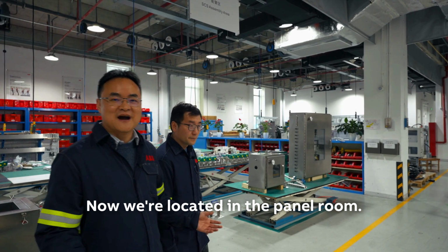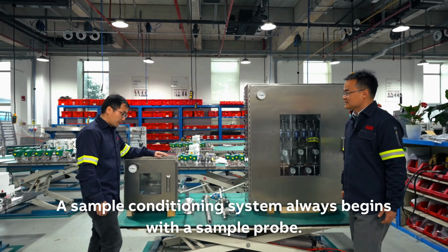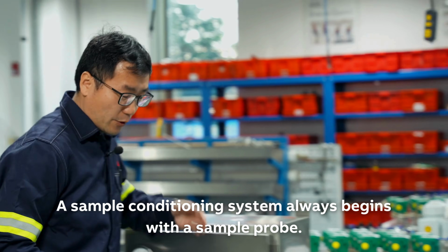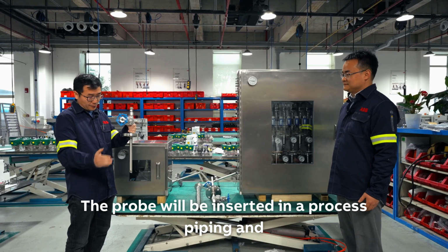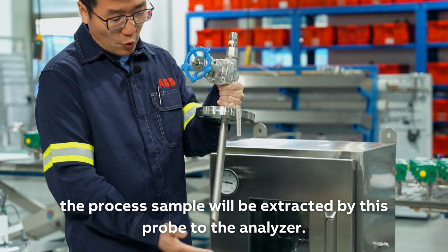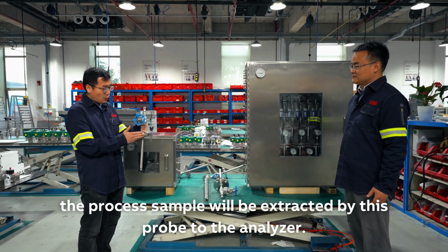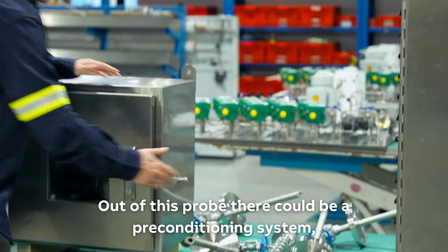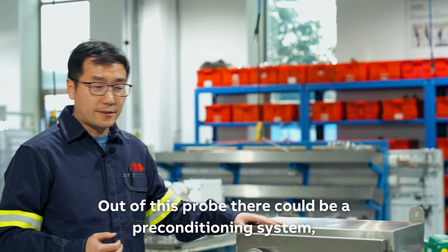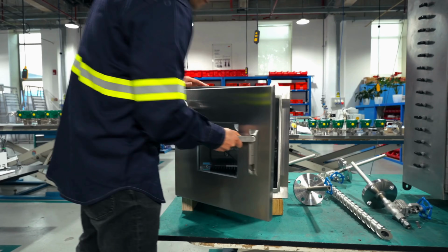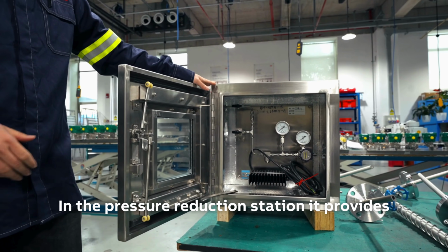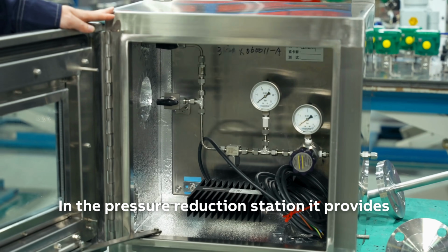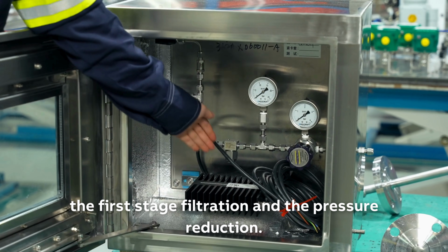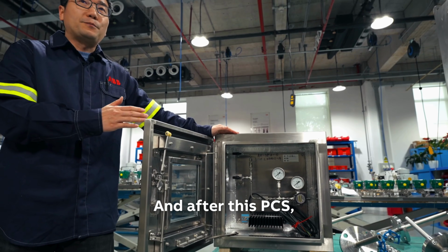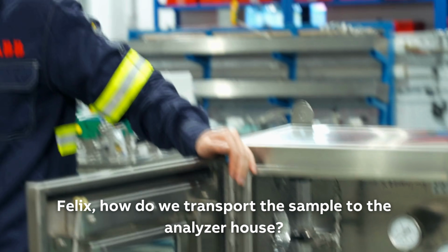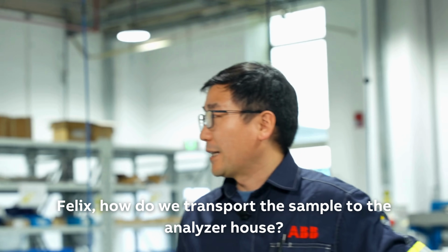Now we're located in the panel room. A sample conditioning system always begins with a sample probe. The probe will be inserted in a process piping, and the process sample will be extracted by this probe to the analyzer. After this probe, there could be a preconditioning system, a pressure reduction station. The pressure reduction station provides the first stage filtration and the pressure reduction. And after this PCS, Felix, how do we transport the sample to the analyzer house?